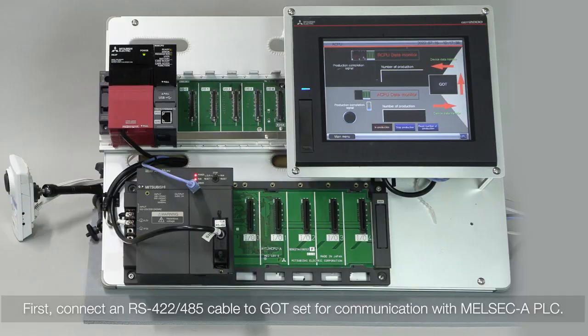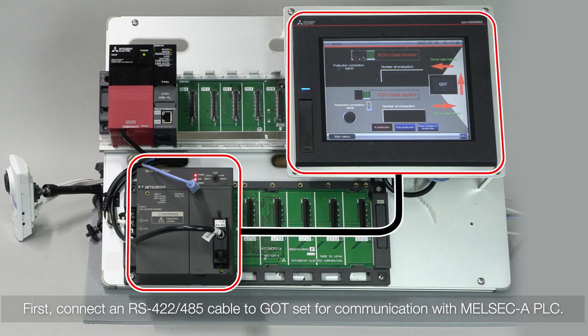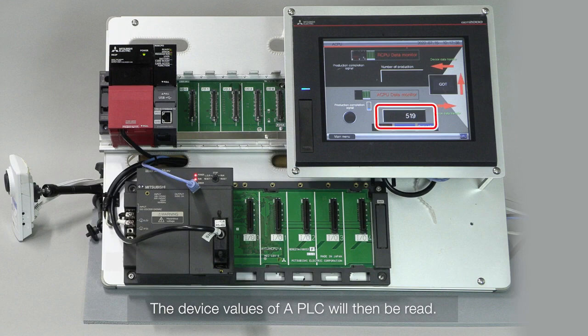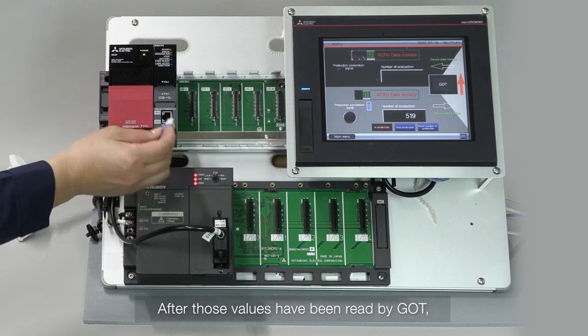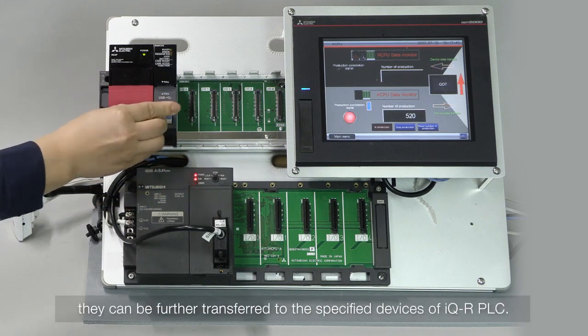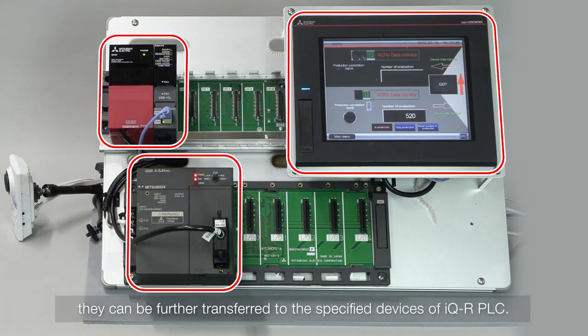First, connect an RS422/485 cable to GOT set for communication with MELSEC-A PLC. Device values of MELSEC-A PLC will then be read. After those values have been read by GOT, they can be further transferred to the specified devices of iQ-R PLC.